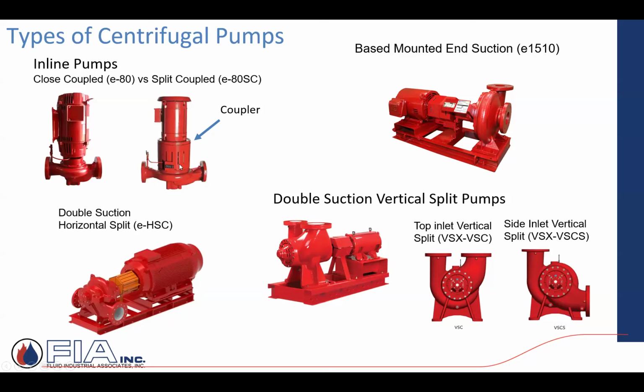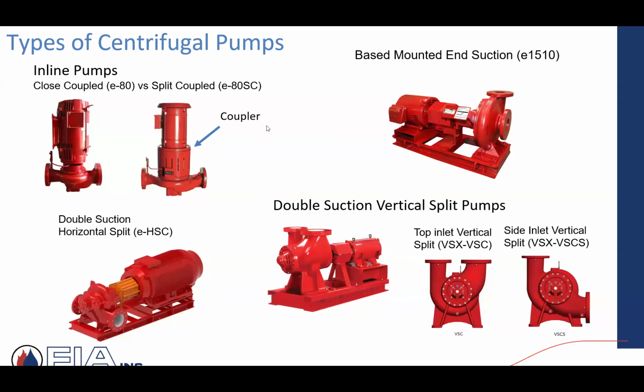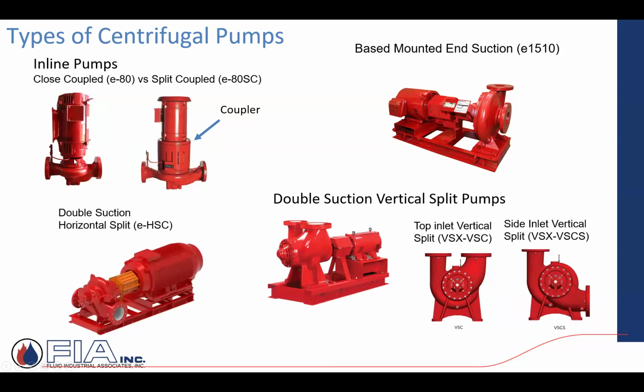So anyways, you were saying, well, split coupled. As you get into some of these larger inline pumps, the horsepower that's required gets very excessive. And at some point, it maybe makes sense to move away from this style and move to more of a base mounting, which we'll get into. But the split coupled allows the service technician down the road, the mechanic that's installing these and then needs to go back and service them, to not have to contend with maybe repositioning or moving that motor. They can open up this split coupler, this enclosure, and have access to the impeller, access to the seal, without having to deal with the motor, whereas this style here, the smaller close coupled, it's a smaller horsepower, so it's not as big of a deal. But if you took that same concept and applied it to this larger capacity, the horsepower they'd be dealing with would be unruly. It'd be very difficult.